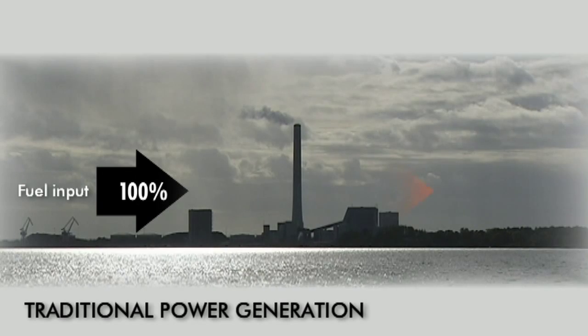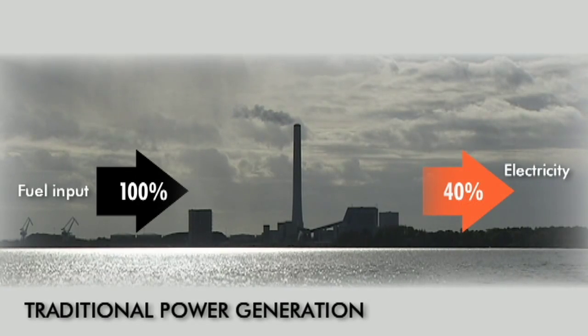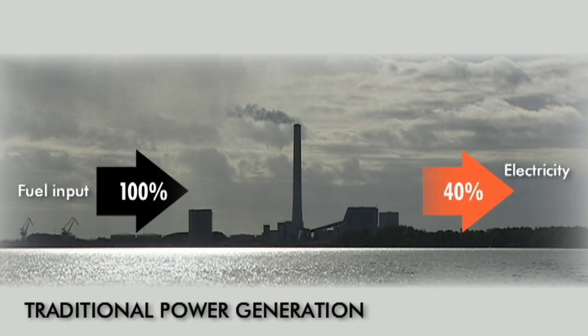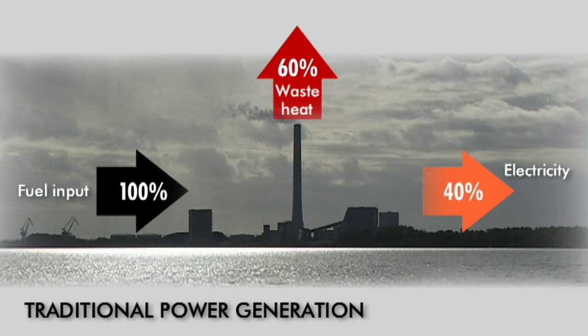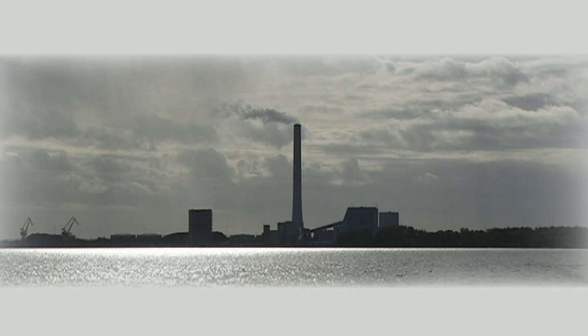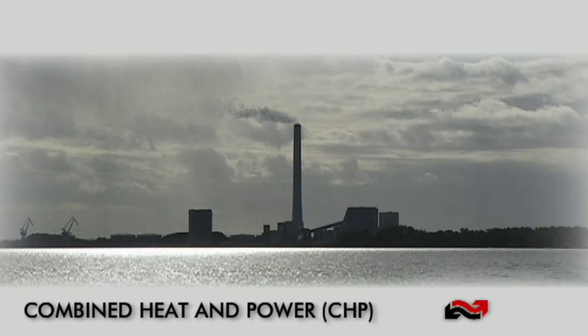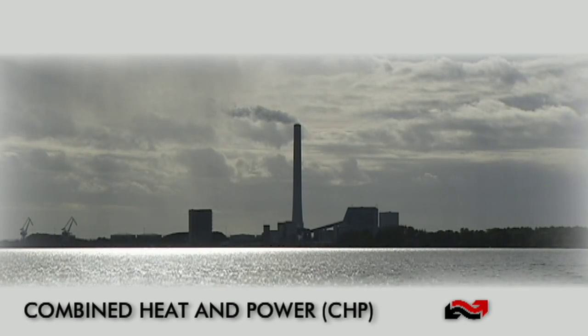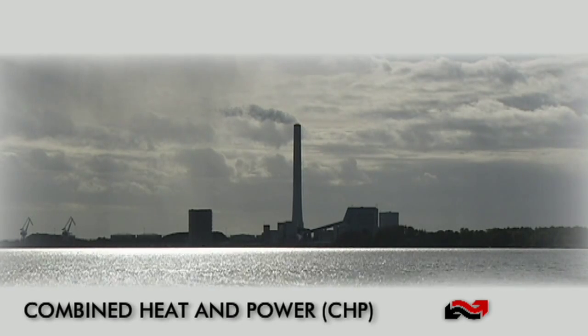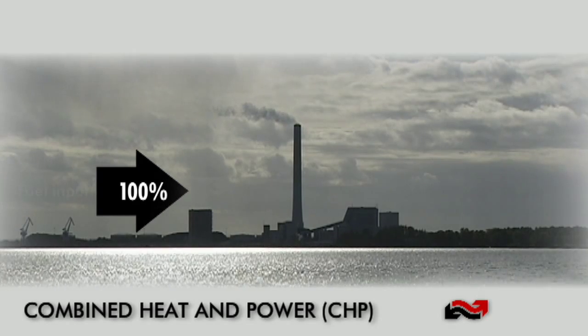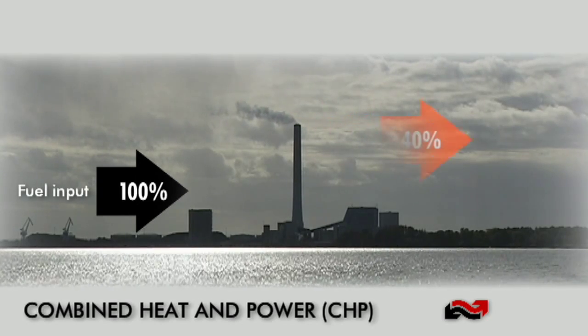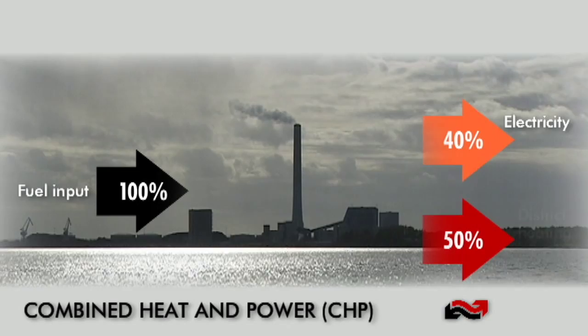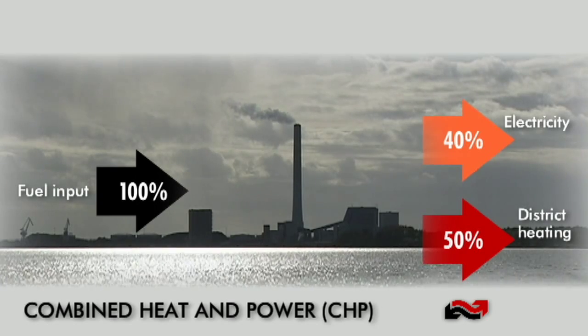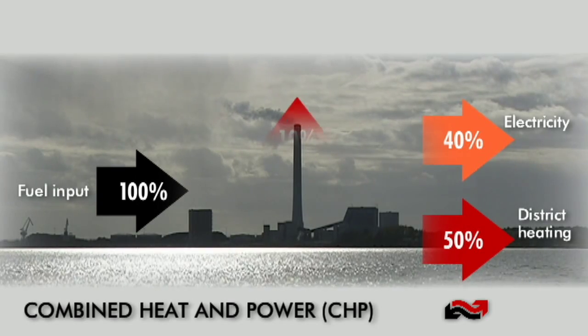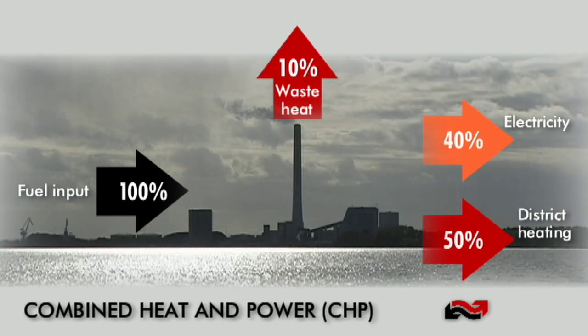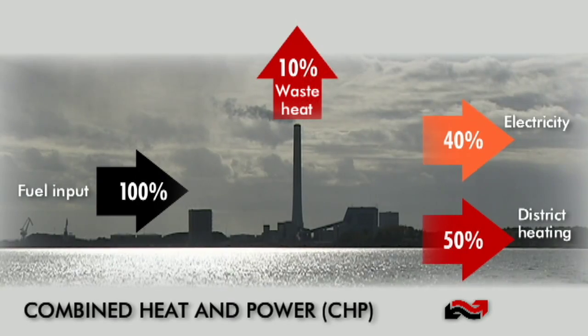Typically, only 40% of the energy consumed is converted to electricity, whilst 60% is wasted as heat loss. A combined heat and power solution, CHP, gives increased energy efficiency. For the same total energy consumption and electricity output, 50% of the energy consumed is converted to district heating, reducing the energy lost as waste heat to 10%.